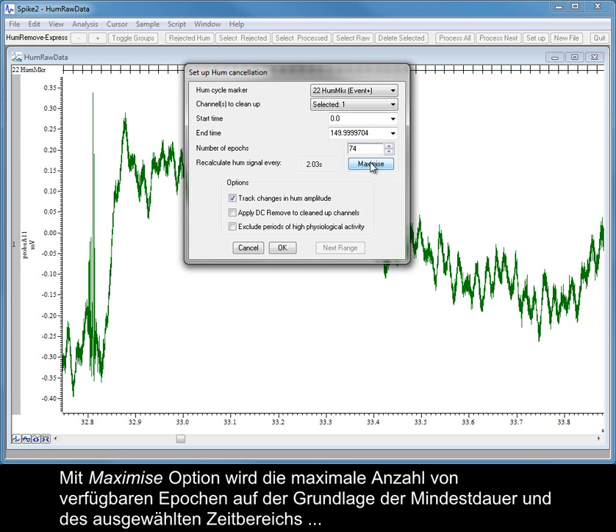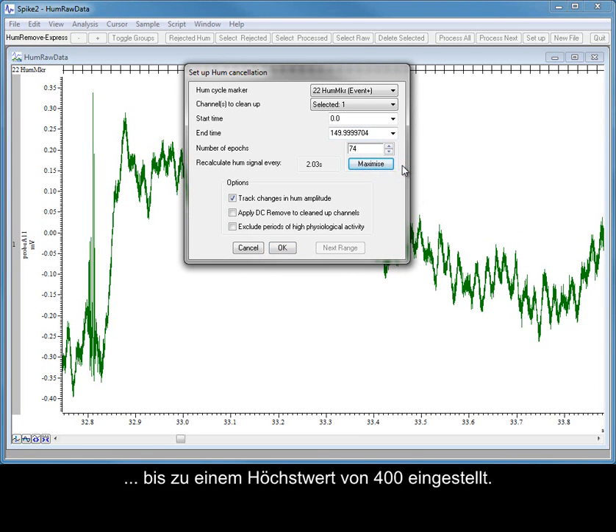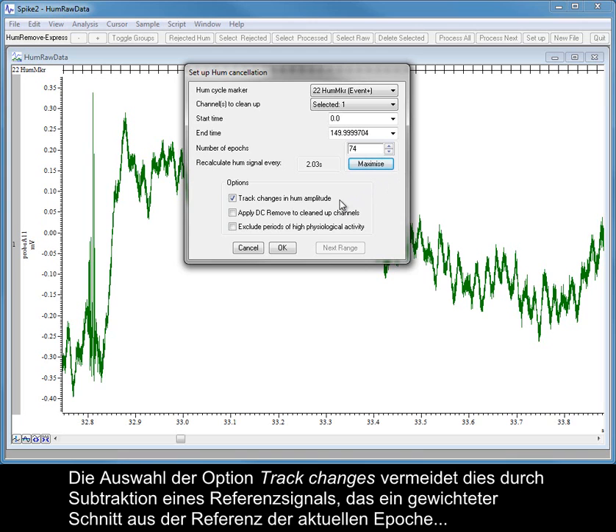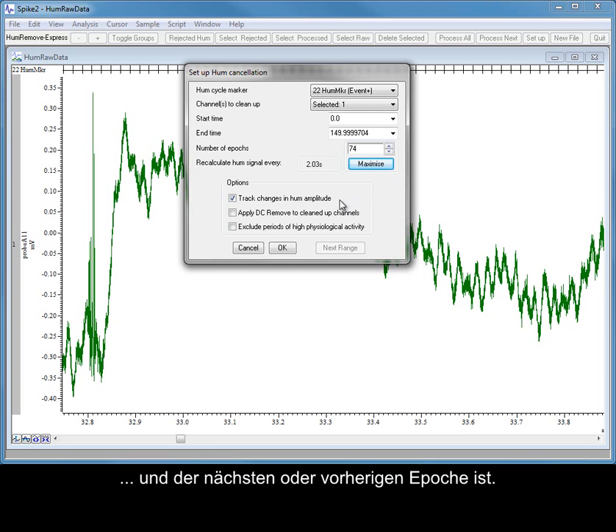The Maximize option sets the maximum number of Epochs available based on the minimum duration and the selected time range, up to a maximum value of 400. When using multiple Epochs, there is the potential to introduce a step change in the reference average and waveform between Epochs. Selecting the Track Changes option avoids this by subtracting a reference signal that is a weighted average of the reference of the current Epoch with that of the next or previous Epoch.